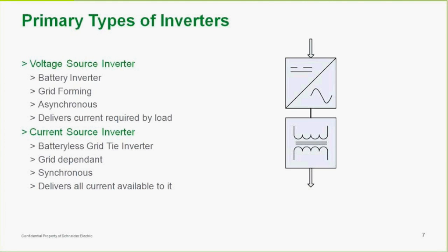This becomes important because another thing customers will say they want to do is, since my batteryless grid tie inverter cannot operate without the grid, and I want it to work when the power goes out, because they just had a power outage and learned for the first time that their batteryless grid tie inverter system does not provide backup, they think they want to just buy a small generator and tie it to the system.